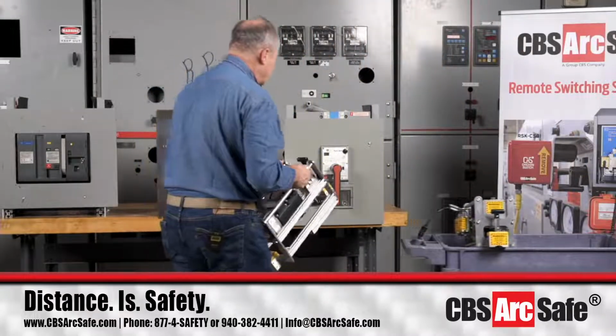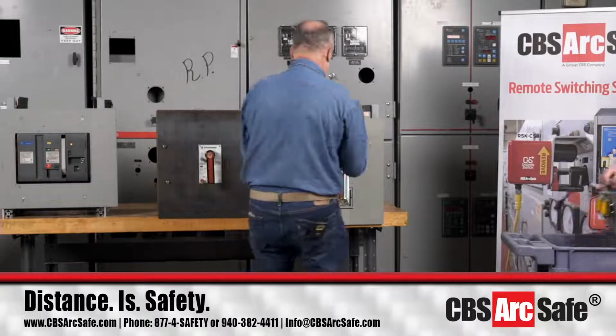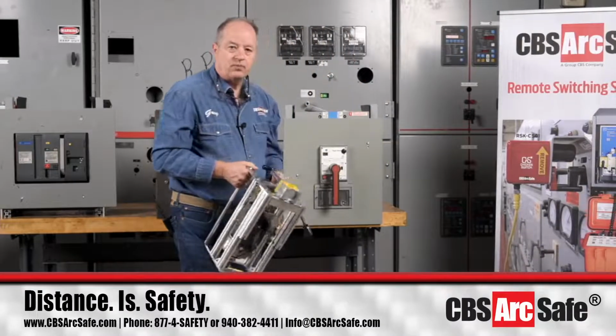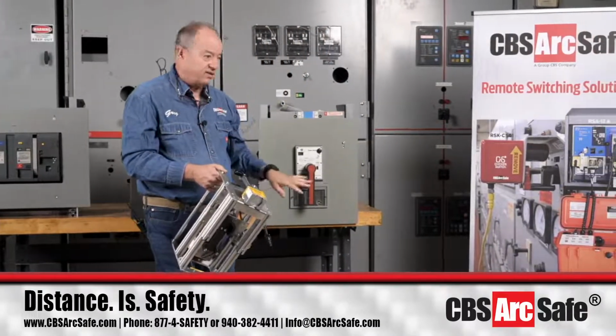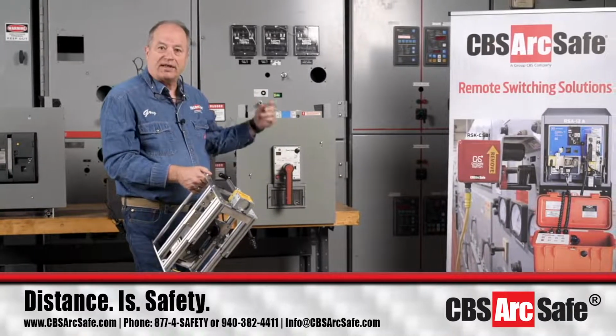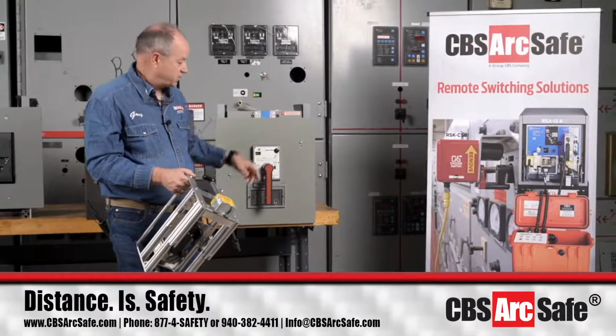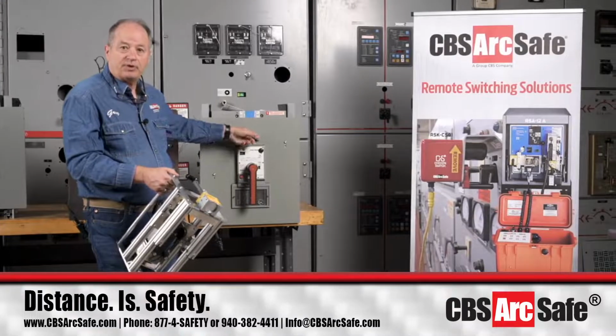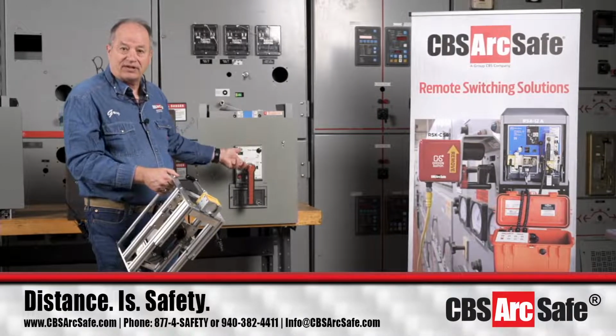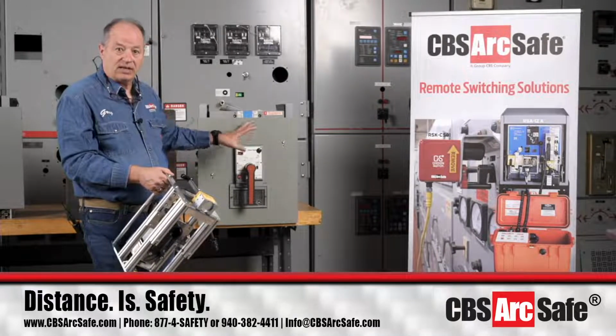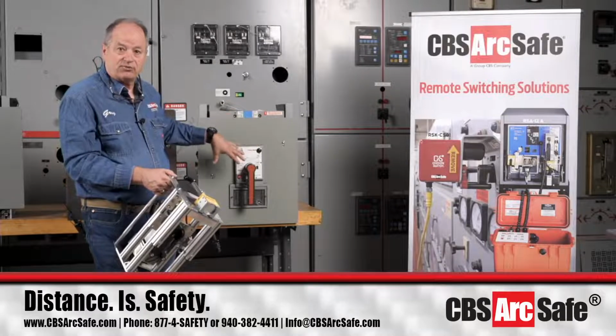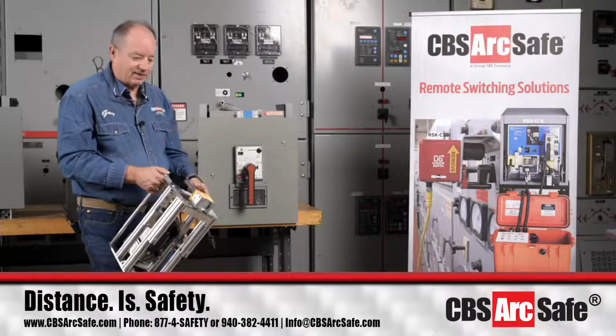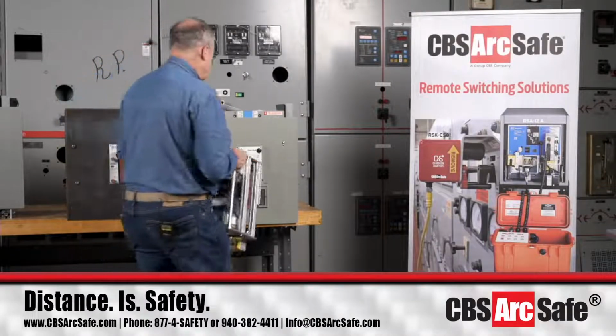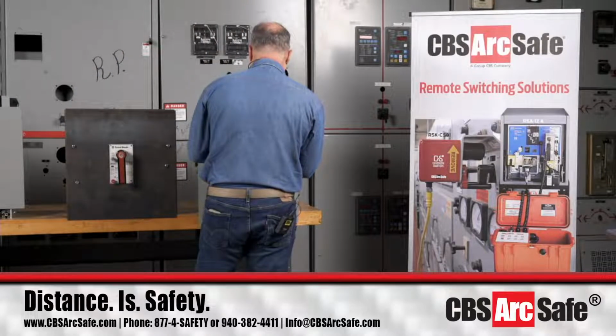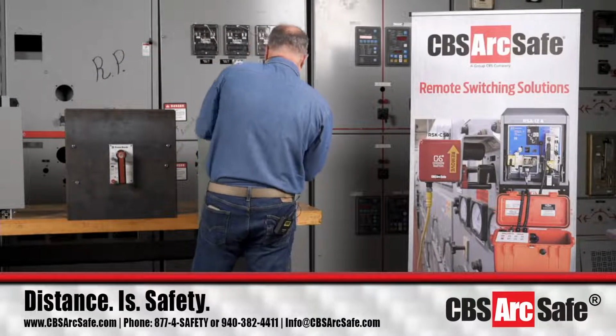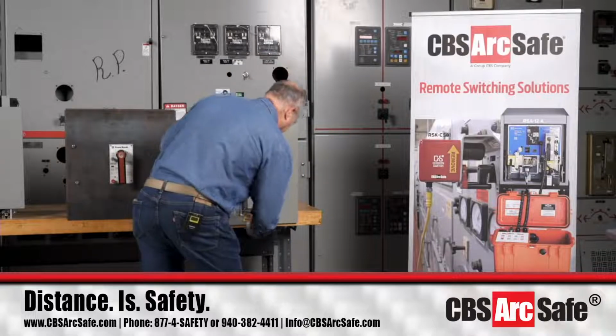This is the 91 AM, and one thing to watch out for on this style of breaker is you can have bottom feed and top feed variations, and your trip and close buttons can get reversed on the face. Again, we need to see the breaker, see which version you've got, and know that so when we get your RSA set up, we do that right. It makes a difference.